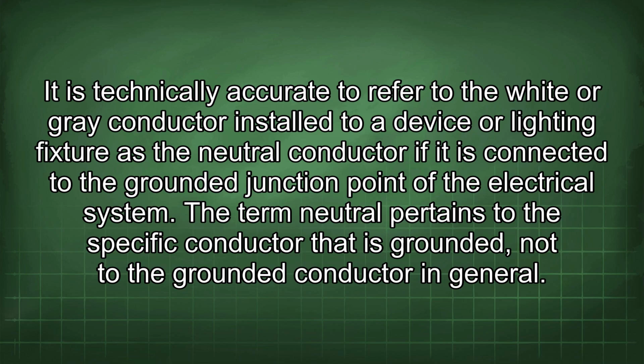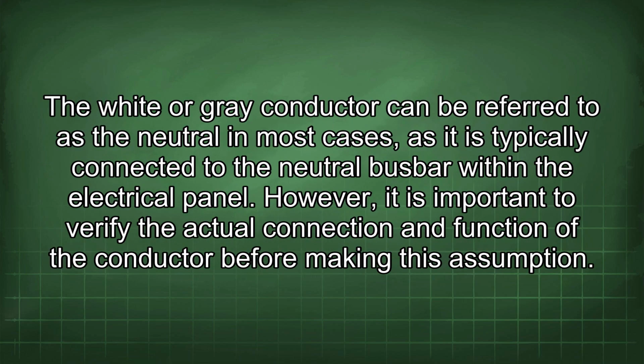The term neutral pertains to the specific conductor that is grounded, not to the grounded conductor in general. The white or gray conductor can be referred to as the neutral in most cases, as it is typically connected to the neutral busbar within the electrical panel. However, it is important to verify the actual connection and function of the conductor before making this assumption.